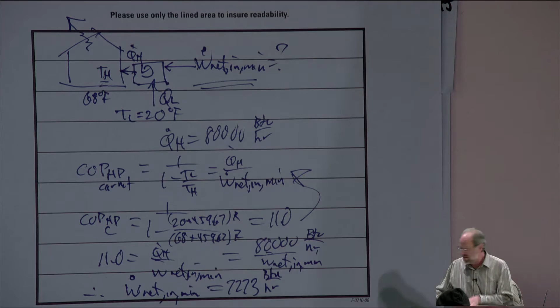Now, frankly, BTUs per hour is an appropriate set of units, but it's not the one that's customarily used in the British system. In the British system of units, what we would typically use is the horsepower. So we would basically divide by 2545. It's actually 2544 point something. And that's going to be the number of BTUs per hour per horsepower. And then this gives me 2.86 horsepower. So the minimum power that this particular heat pump could require is 2.86 horsepower.